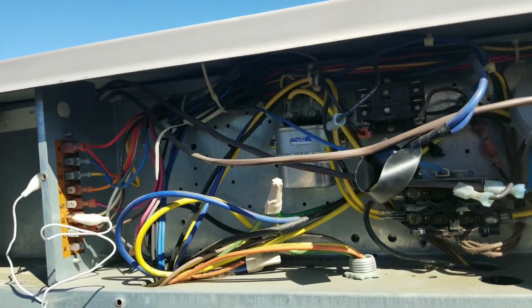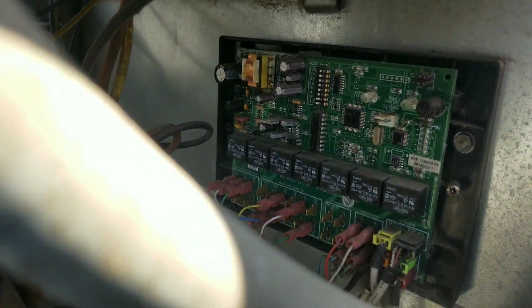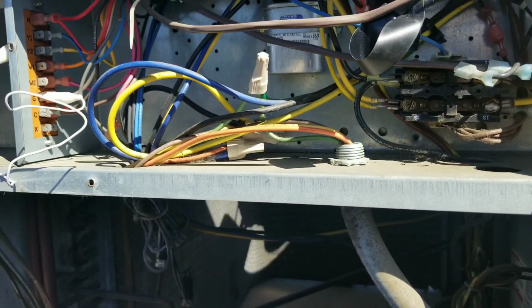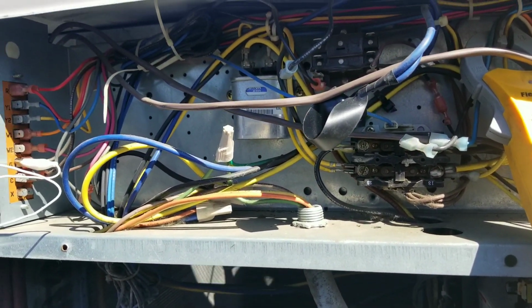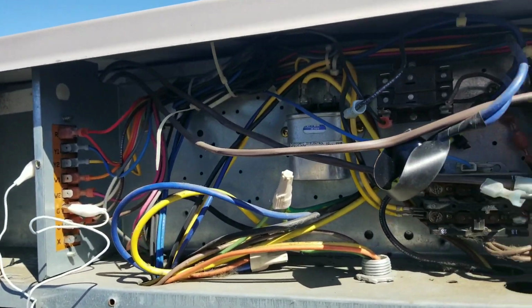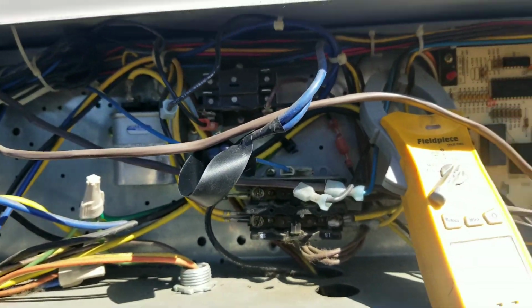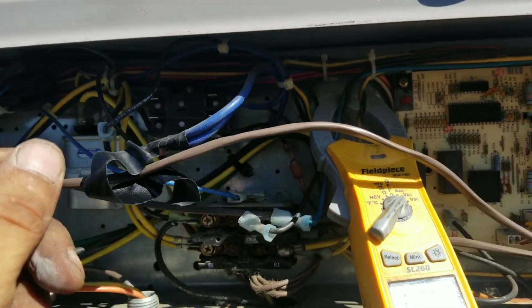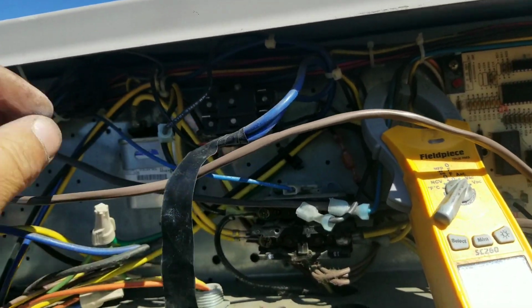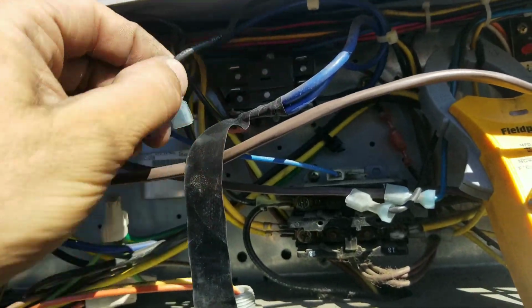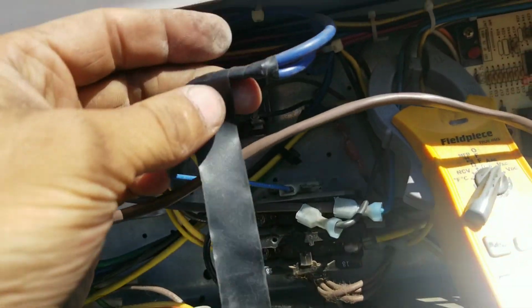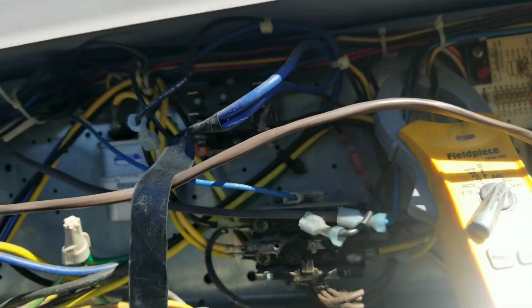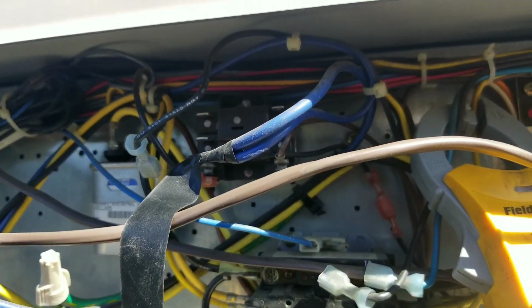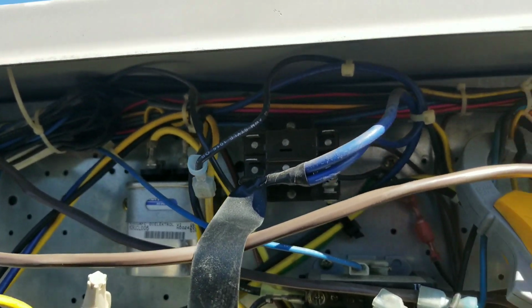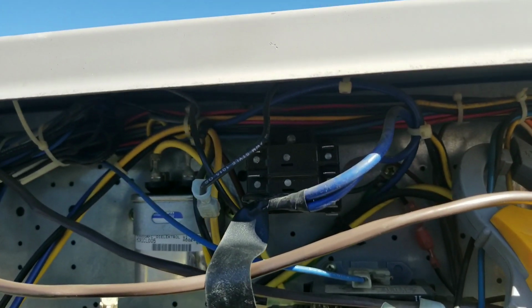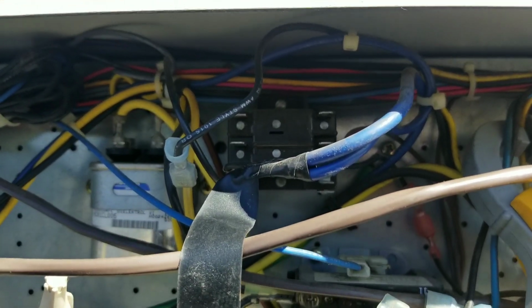And if you're wondering why my compressor came on, this particular unit is operated by an energy management company. So there probably is a call for cooling downstairs. I just bypassed it when I started just in case there wasn't a call for cooling. And another tip, if you guys ever want to do what I did here, make sure you tape up some of your terminals. Like these ones I wasn't too concerned about, but this one didn't have any plastic insulation on it, so I taped it up to make sure it didn't short to ground. So if you're gonna do experiments like that under voltage, be safe about it, okay? All right, let me go grab a relay and we'll pop it in there and see what happens.